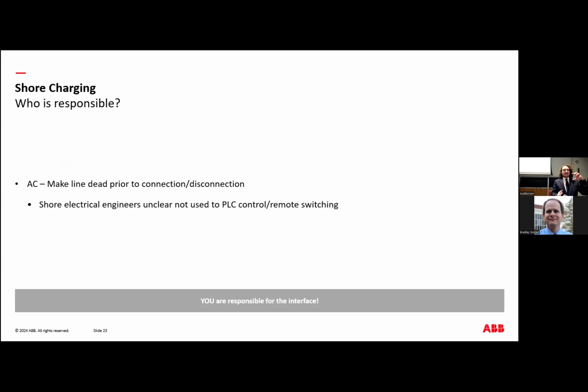Making an automated power connection system is also not a very common thing for shoreside electrical engineers, so they aren't used to it. We actually had a project where things were installed that didn't include the contactor and the PLC necessary to switch the line at every connection, and we've had to put in a whole other switchboard on land.